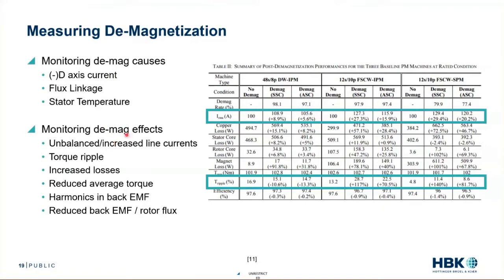Demagnetization has a variety of effects: unbalanced line currents, torque ripple, increased losses, reduced average torque, harmonics in the back EMF, reduced back EMF, and reduced rotor flux.